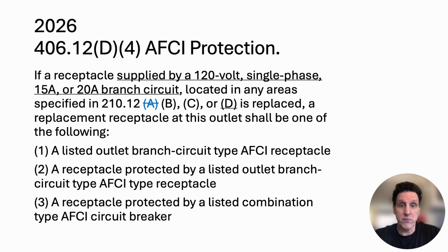That's it. It's really only two options: an AFCI receptacle protecting another AFCI receptacle or protecting that receptacle that you've replaced, or an AFCI breaker, a combination type AFCI breaker.